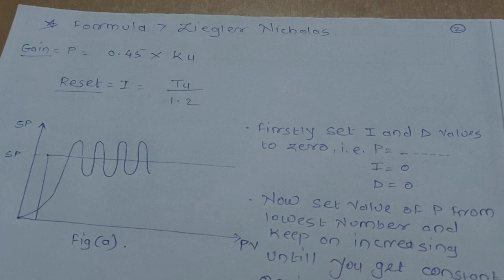Now we will see Ziegler-Nichols equation where gain parameter P is equal to 0.45 into Ku, and reset parameter I is equal to Tu divided by 1.2. Now we have to find out the value of Ku and Tu.